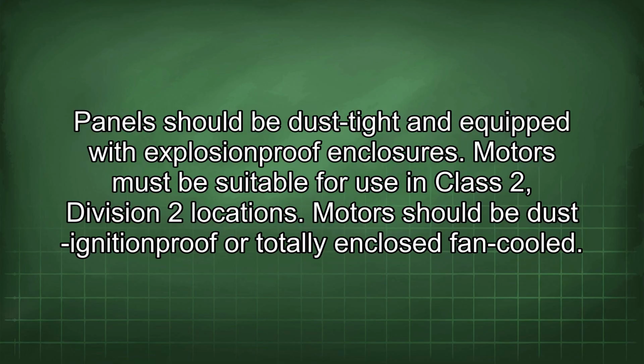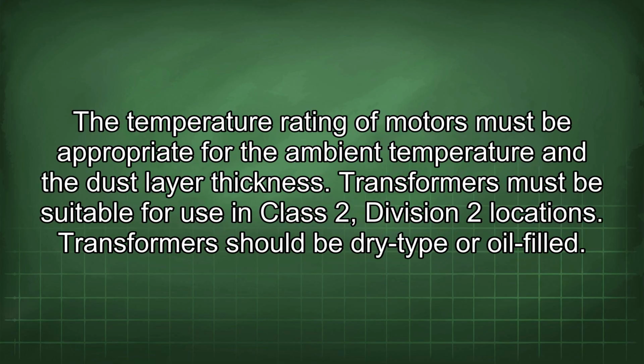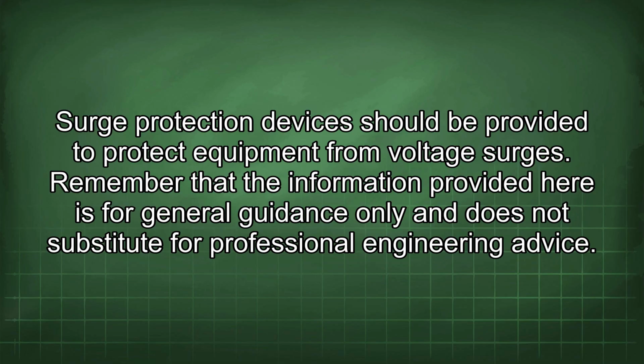Motors must be suitable for use in Class 2, Division 2 locations. Motors should be dust ignition-proof or totally enclosed fan-cooled. The temperature rating of motors must be appropriate for the ambient temperature and the dust layer thickness. Transformers must be suitable for use in Class 2, Division 2 locations. Transformer should be dry-type or oil-filled. Surge protection devices should be provided to protect equipment from voltage surges. Remember that the information provided here is for general guidance only and does not substitute for professional engineering advice.